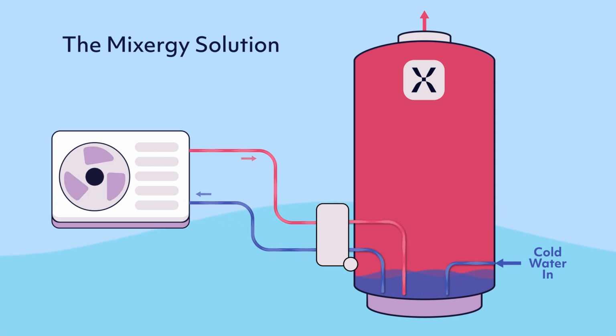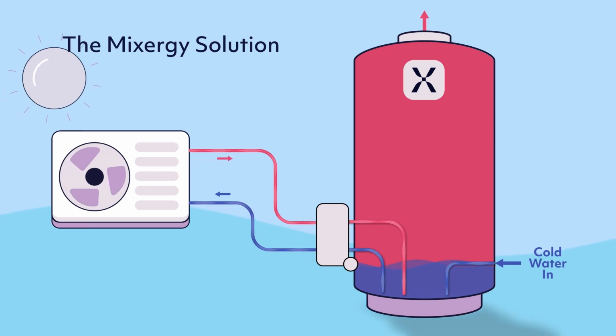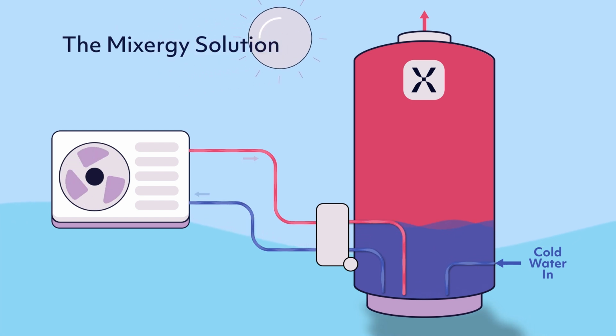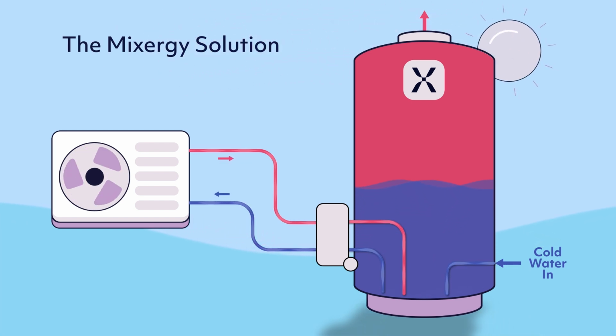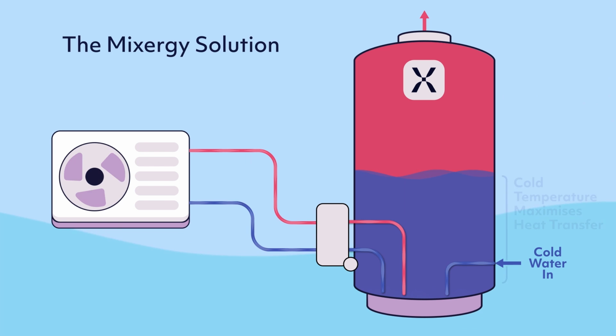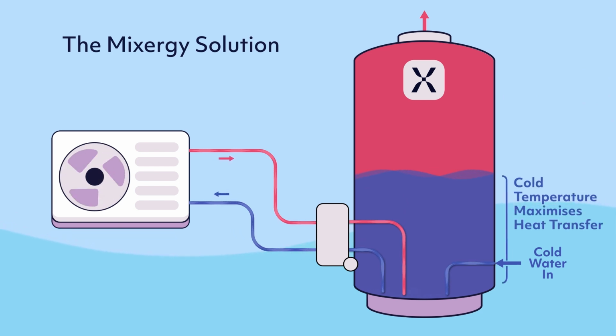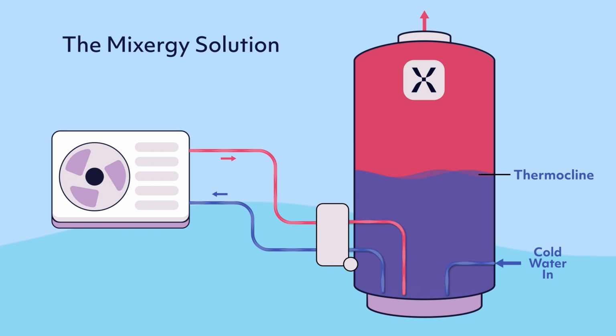The advantages of plate heat exchangers increase further when heating up a cylinder that's already partially heated. As before, about half the hot water in the cylinder is used throughout the day. When reheating through the plate heat exchanger, however, we are always transferring energy from the coldest part of the cylinder. This means that we avoid the problems of coil lockout and continue heating with the best possible COP.